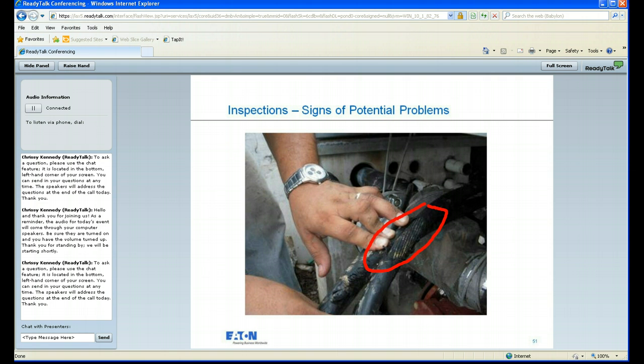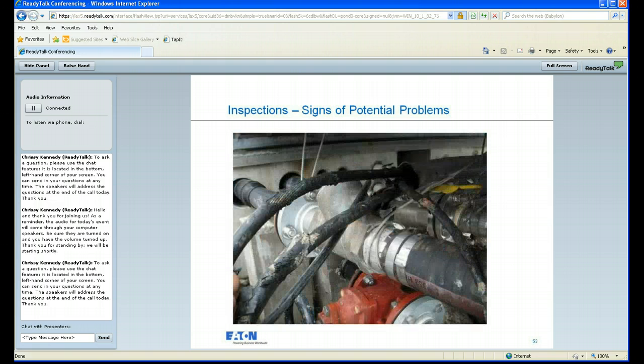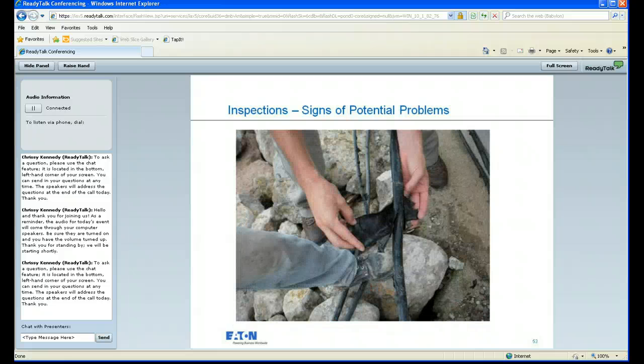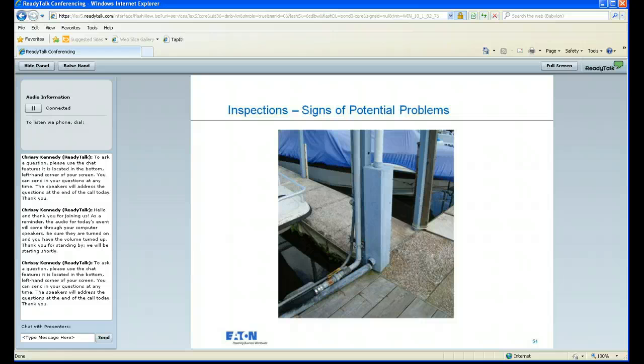Again, with exposed cables, anything like this where you can see oxidation or rusting of the internal metal conductors is a sign of a potential fire hazard, a potential problem. In a similar picture here, it looks like the wires have been run between those gas lines or sewer lines in the middle. That needs to be replaced right away. Again, you've got some cabling here where the jacket appears to be starting to wear off. Once those conductors are exposed, that needs to be taken care of right away.